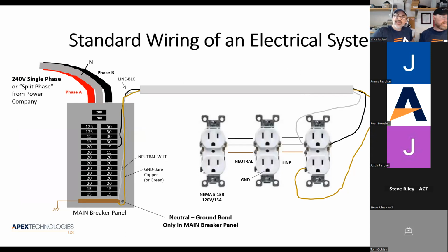Unless you specify otherwise, this is how an electrician is going to hook up your outlets in your equipment closet, right? They are going to most likely use a 15 amp circuit. The black wire is the energized wire, the hot wire. It gets hooked to the circuit breaker, which is connected, of course, to this black phase B here, right? The white wire is the neutral wire. It's going to be connected to a bus bar, right? And this bus bar is also connected to the neutral coming from the transformer, but it also goes into ground rods for lightning protection.